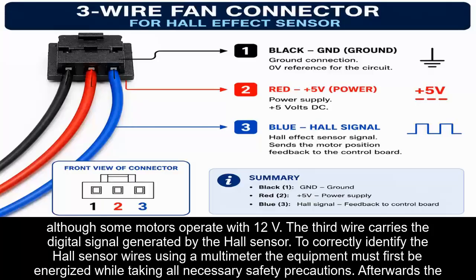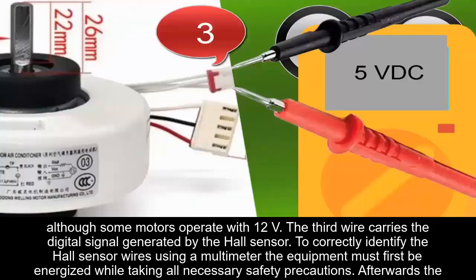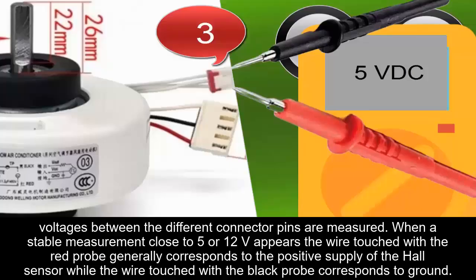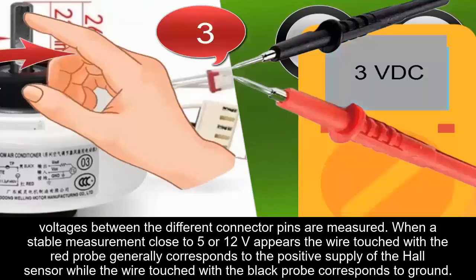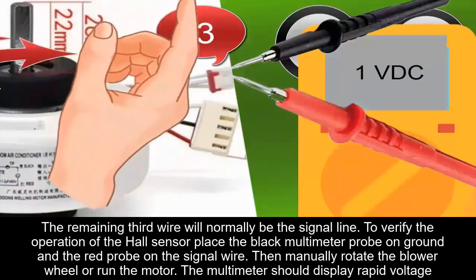To correctly identify the Hall sensor wires using a multimeter, the equipment must first be energized while taking all necessary safety precautions. Afterwards, the voltages between the different connector pins are measured. When a stable measurement close to 5 or 12 volts appears, the wire touched with the red probe generally corresponds to the positive supply of the Hall sensor, while the wire touched with the black probe corresponds to ground. The remaining third wire will normally be the signal line.